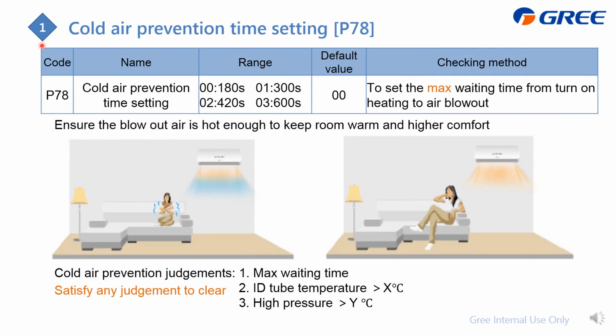Cold air prevention time setting, P78. For this one, the purpose is that when you turn on the indoor unit for heating, the indoor unit will not blow out air immediately, because it needs to make sure it is hot enough to avoid blowing out cold wind, just like this. And there are two judgments. First is the inside temperature, which is detected from the indoor tube, or the high pressure. When we meet this requirement, we will turn on the fans to blow out the air. And the next is the max waiting time. For this P78, what you can adjust is this one.